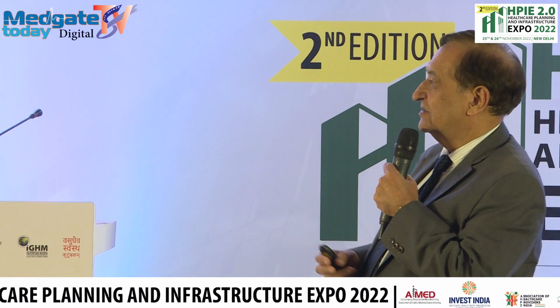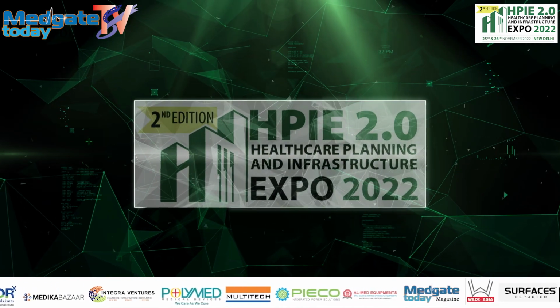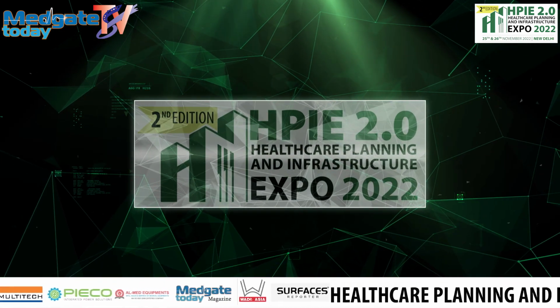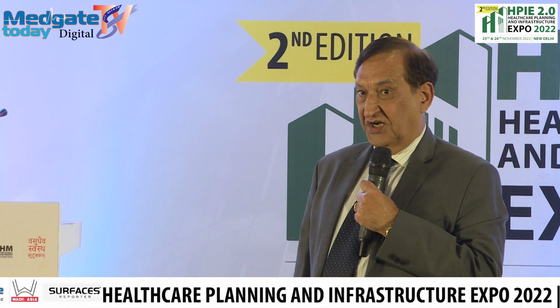Then this is a new delta T. This is ASHRAE standard 90.1, where it says the temperature difference between the inlet and outlet of a cooling coil, we should take it as 15 degree, not 10 degree. Earlier, whatever system the HVAC consultants were designing, they were doing it on a 10-degree temperature difference, which is called delta T. So now they have a new standard where they say you take it to 15 degree, not 10 degree. And what is the advantage of taking it to 15 degree? That I'll show you in the next slide.